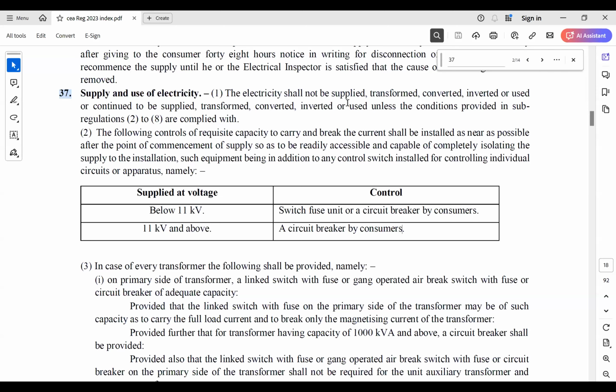And in the earlier 2022 draft or 2021 draft, which the CEA had published, they had given a draft wherein up to a 1250 kVA transformer for 11, 22, 33 kV consumers, it was a switch fuse unit option or a circuit breaker option. Now suddenly, abruptly, overnight, they have changed the law to 11 kV and above circuit breakers. But on ground, there are a lot of problems which are coming up due to this.